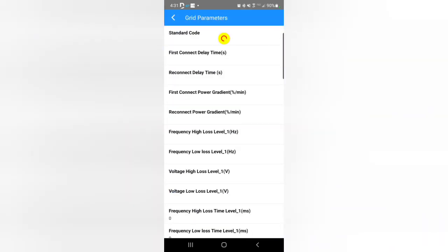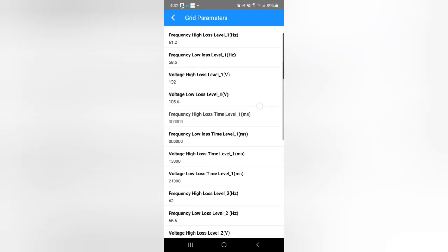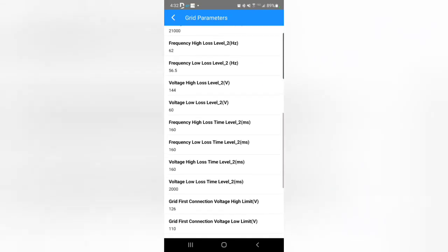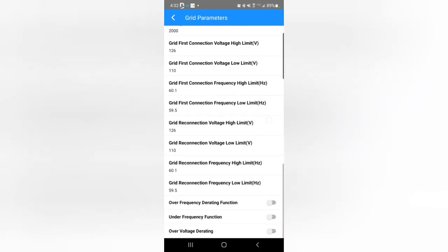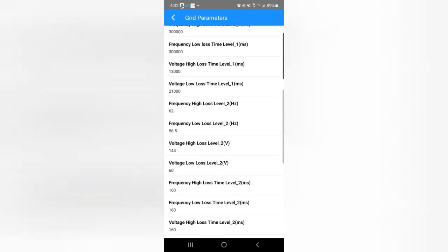All your grid parameters. So first time connect, I changed that to 30 seconds from 60, and then reconnect delay, I just have 15 seconds, and it'll just count down from 15 instead of taking like the whole minute that it's preset at. But yeah, you can go through all your different settings here and change those if you need to.